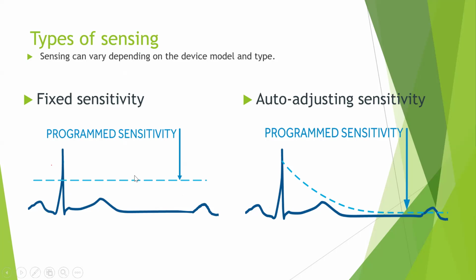While the defibrillator, on the other hand, I will give you another example later on, uses what we call auto-adjusting sensitivity. It starts at a peak and gradually reduces the sensitivity number to be able to detect any activity, because sometimes in ventricular fibrillation the amplitude of the wave will be very low, and as a result you require the device to be able to see that. So that's why the ICD uses what we call auto-adjusting sensitivity.